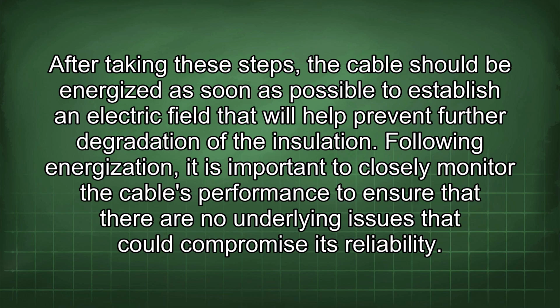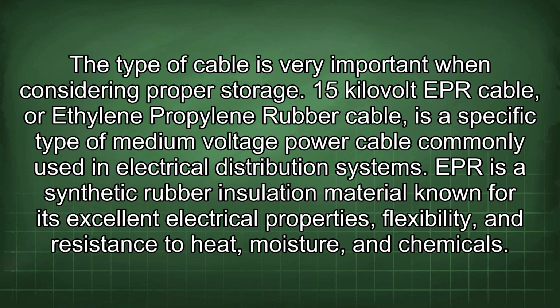Following energization, it is important to closely monitor the cable's performance to ensure that there are no underlying issues that could compromise its reliability. The type of cable is very important when considering proper storage. 15 kilovolt EPR cable, or ethylene propylene rubber cable, is a specific type of medium voltage power cable commonly used in electrical distribution systems. EPR is a synthetic rubber insulation material known for its excellent electrical properties, flexibility, and resistance to heat, moisture, and chemicals.